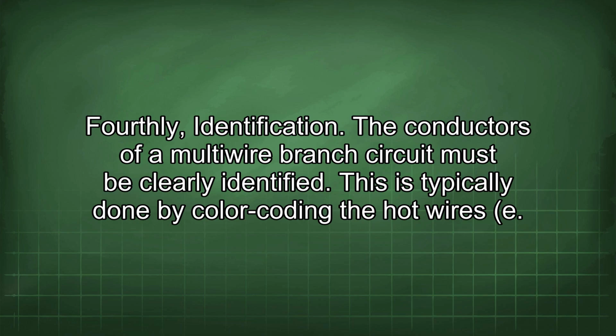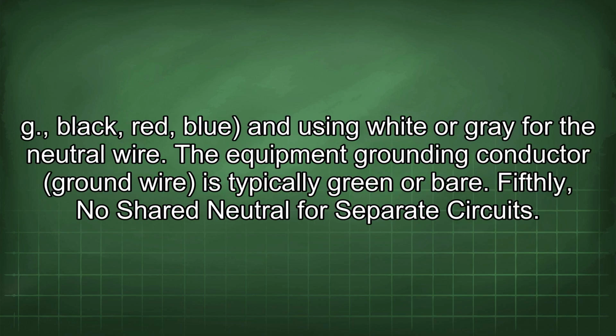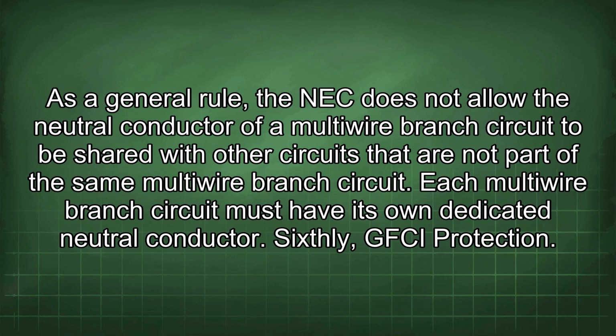This is typically done by color coding the hot wires, for example black, red, and blue, and using white or gray for the neutral wire. The equipment grounding conductor, the ground wire, is typically green or bare. Fifthly, no shared neutral for separate circuits. As a general rule, the NEC does not allow the neutral conductor of a multi-wire branch circuit to be shared with other circuits that are not part of the same multi-wire branch circuit. Each multi-wire branch circuit must have its own dedicated neutral conductor.